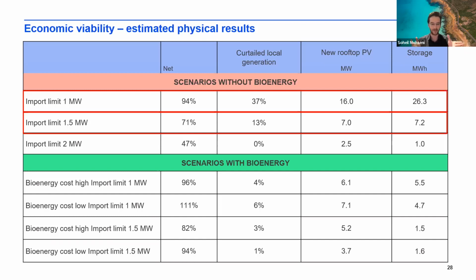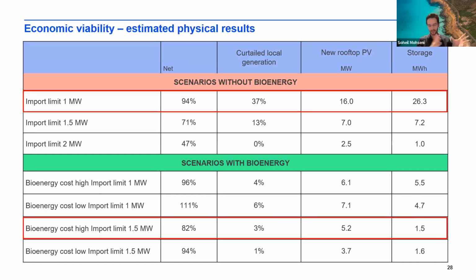And this is really a big value both for solar and for storage. For example, just to give you an indication, the Malakuta community has just recently installed 1 megawatt hour of battery, and so 26 megawatt hours of storage. It's insane, and I know no way to finance it. But on the positive side, 26 megawatt hours of storage provides approximately 12 hours of battery autonomy. And this means that with the battery alone, you can sustain the loads for about 12 hours. And this is, of course, a significant resiliency benefit, but it's not realistic from a cost perspective, really.